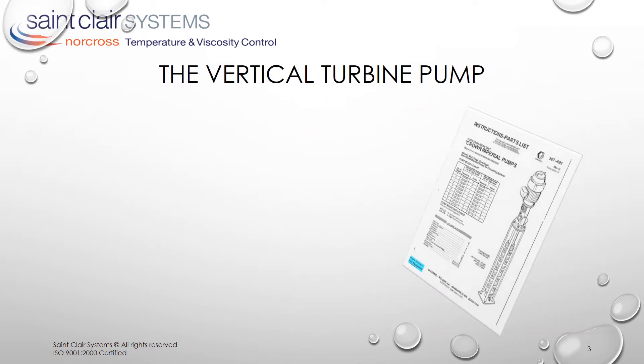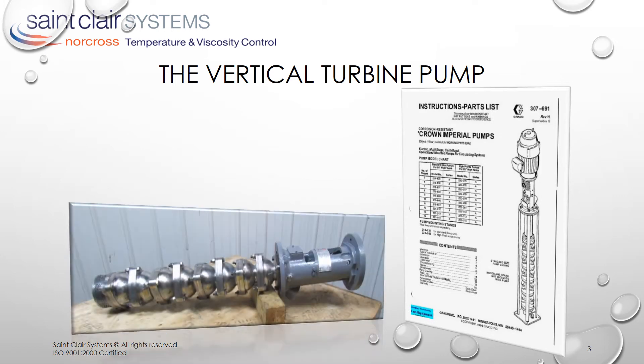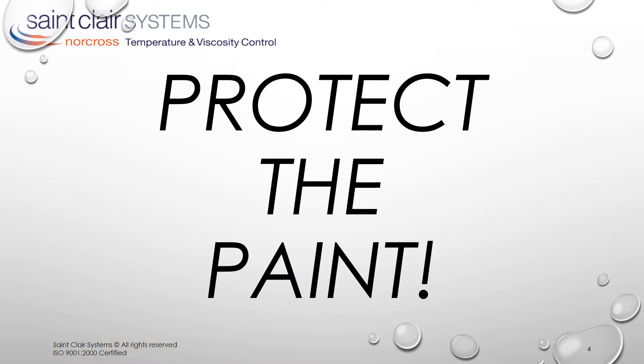But a major culprit was the vertical turbine pump. Depending on the number of bowls and the system pressure — often a function of system length — these pumps can add as much as 10 to 15 degrees Fahrenheit to the paint on each pass-through. And this kind of heat buildup could quickly drive off solvent and even cook the paint. And paint was expensive back then, just like it is today. So the mantra became: protect the paint.